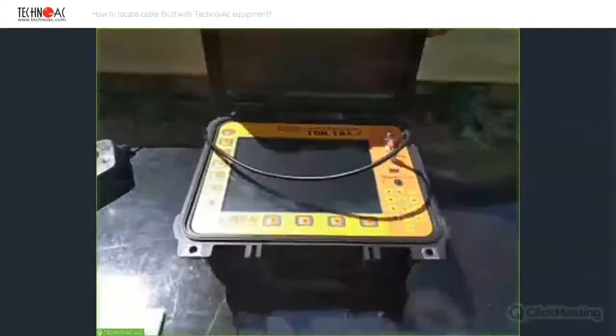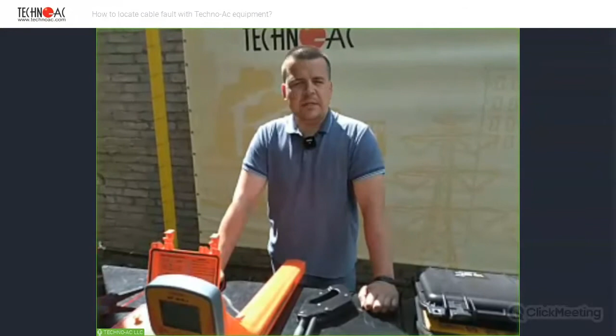I will explain the operation sequence for every one of these devices, and we will be able to locate cable faults with all of them. As you can see, we don't have much equipment for cable fault location on our table today, but all this equipment represents two main approaches of TECHNO-AC for cable fault location. First of all, you have to do your best in order to save the cable. You know that there are several methods of cable fault location, and one of them is high voltage surge cable burning. It means that you send a high voltage pulse inside the cable and you burn the cable till the fault is visible and detectable. In TECHNO-AC, we also have this equipment for Russian market, and in most cases for older cables and for less high quality cables, this is the only way. High voltage surge pulse is the only way.